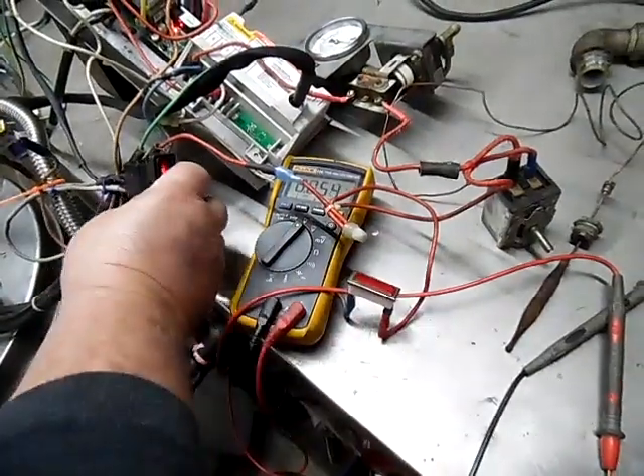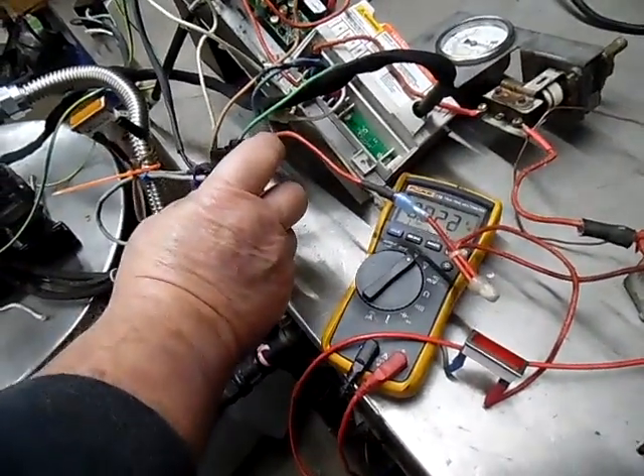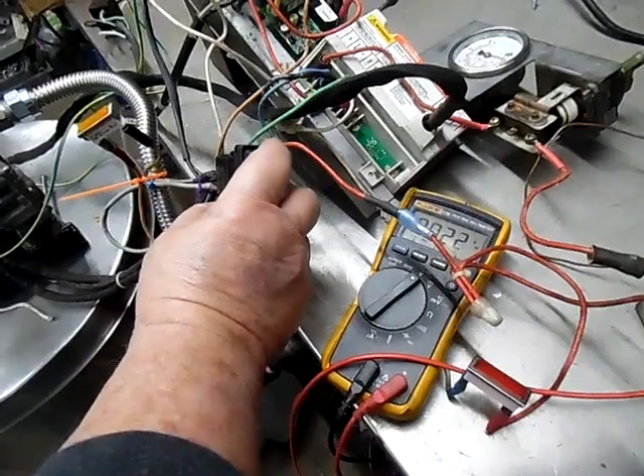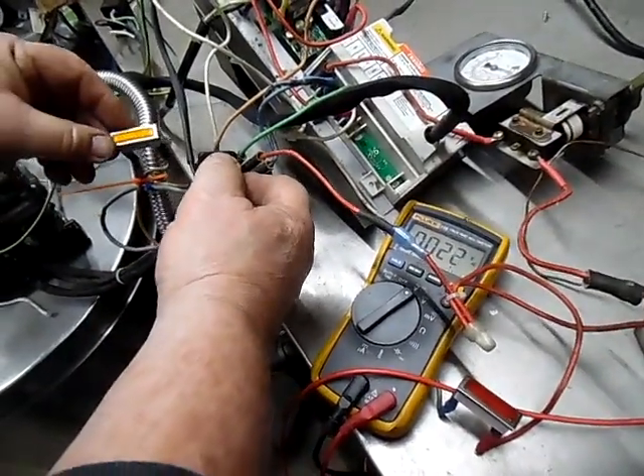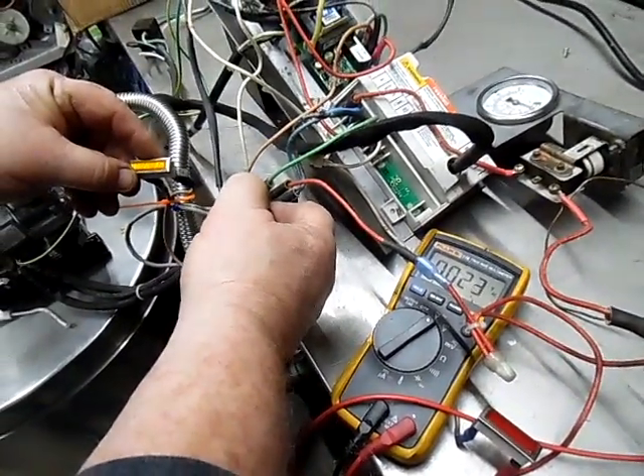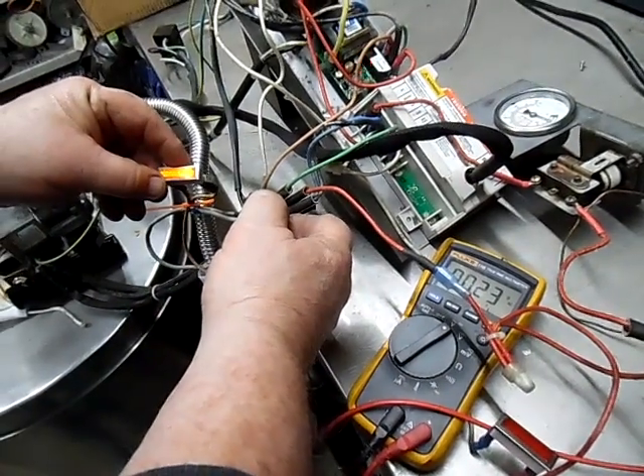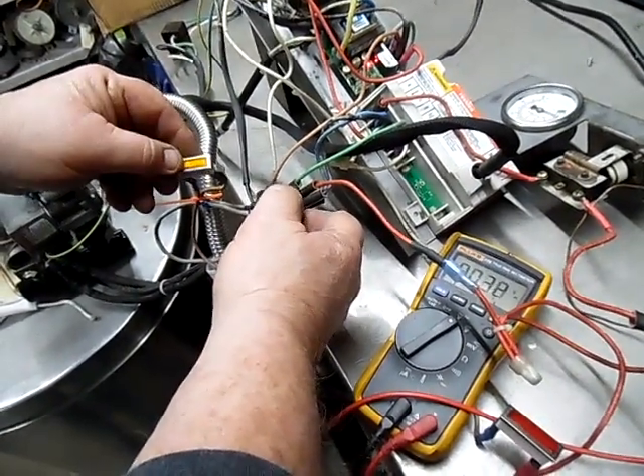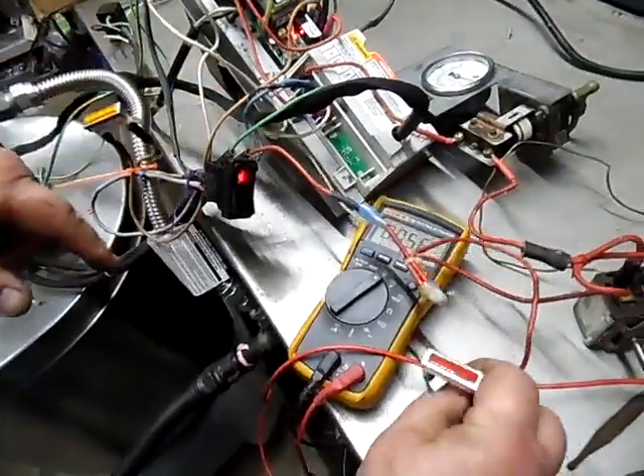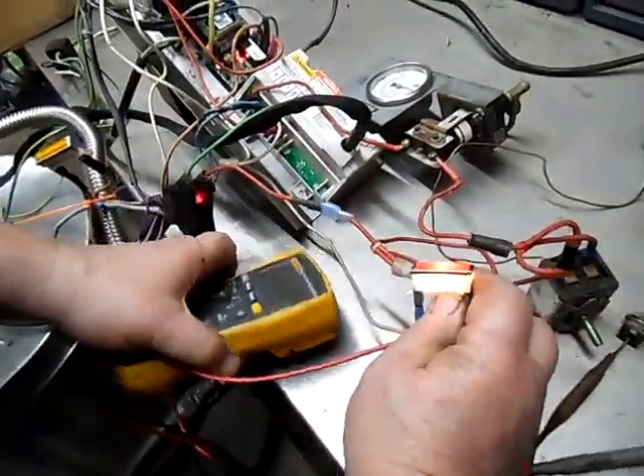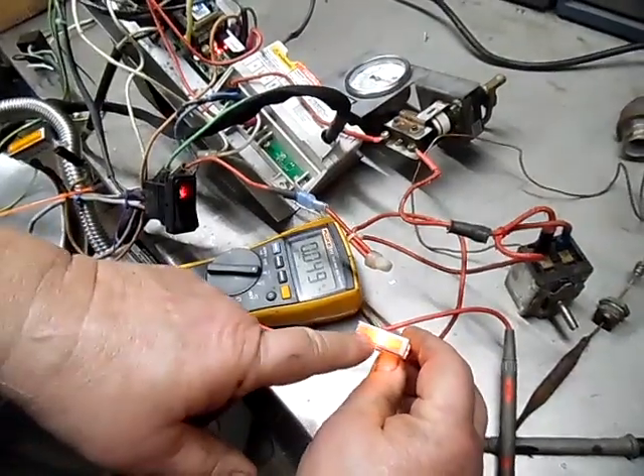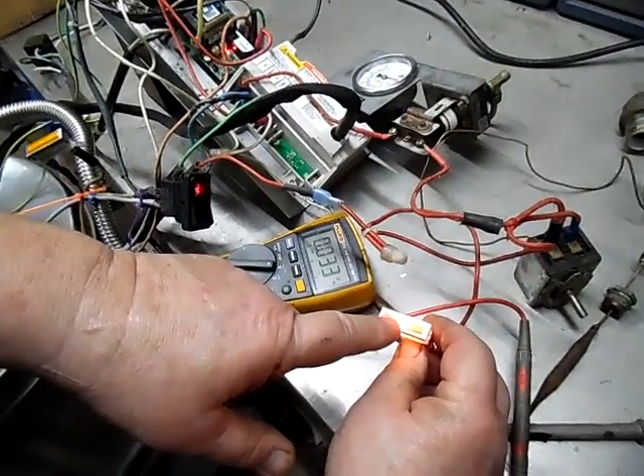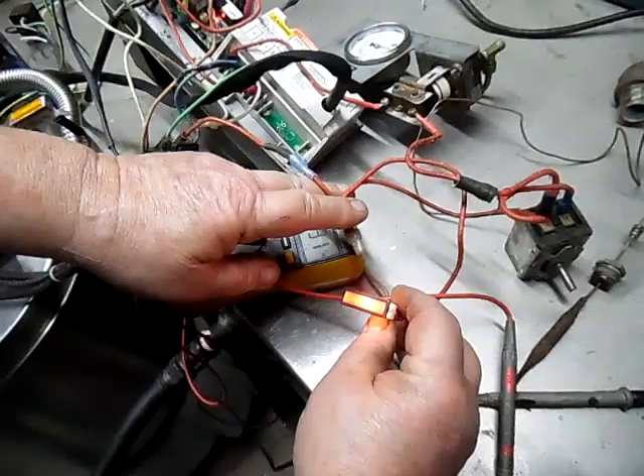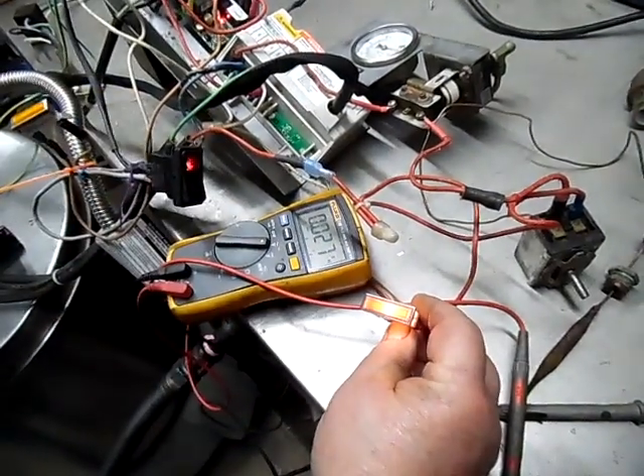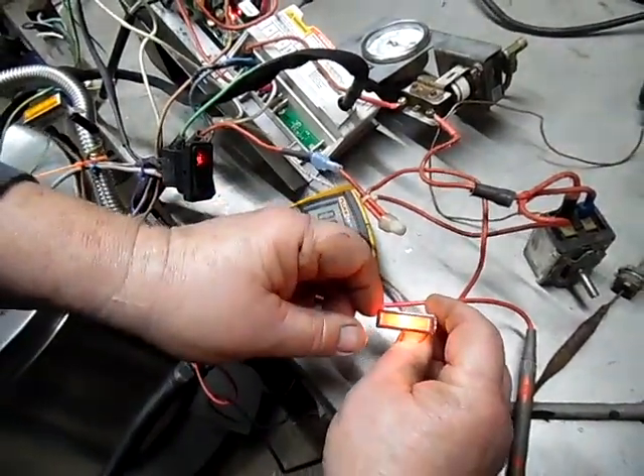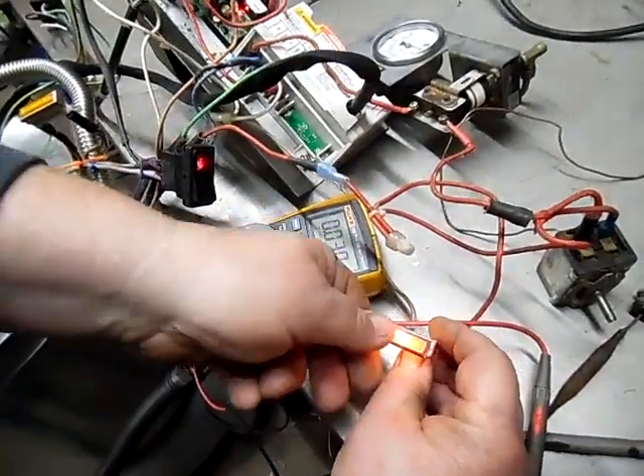Let me show you one thing I didn't talk about. I'm going to turn the system on normally. As soon as I turn it on, watch the amber light. That's your water level light. It comes on. Since we grounded the wire so it's satisfied, now turn stuff on here. And as soon as the main valve comes on, then we get the light for the main burner. So this is tied into the same line to MV. As soon as it gets voltage to the gas valve, you should see a red light going on, providing your neutral wire is good.